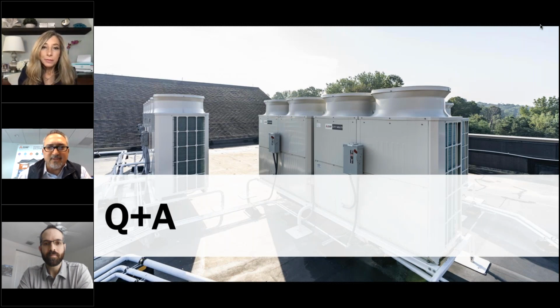So for a senior living building that is using one-to-one mini splits or variable capacity heat pumps throughout the majority of the building, any part of the building that needs ventilation, you have to have a dedicated outside air system or an ERV to bring it in. The reason I spent a couple of slides on that is we always get those types of questions. Going back to the presentation, for every building that requires ventilation air, you need to look at that building specific to how you're going to use it.